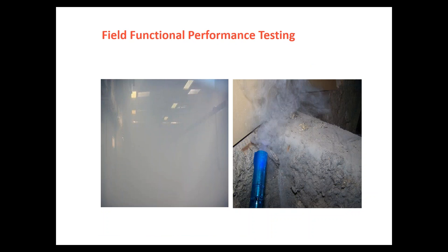We also want to look at air leakage. For an Army Corps building, they have a pretty stringent air barrier set of testing requirements — whole building air barrier testing where you fill the building with smoke and run blower doors, looking visually for leaks. Then a second phase of the test gives you a quantifiable amount of leakage. In localized conditions on existing buildings, we may be asked to look at complaints of draftiness using a small handheld device to create smoke and determine if those interfaces are actually leaking air.